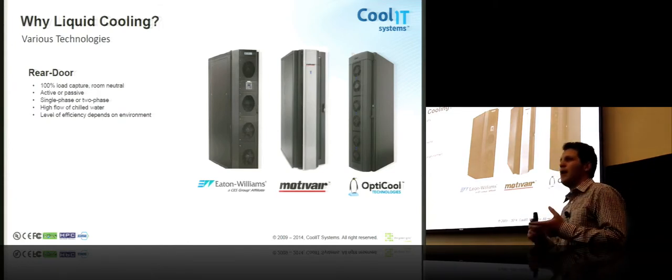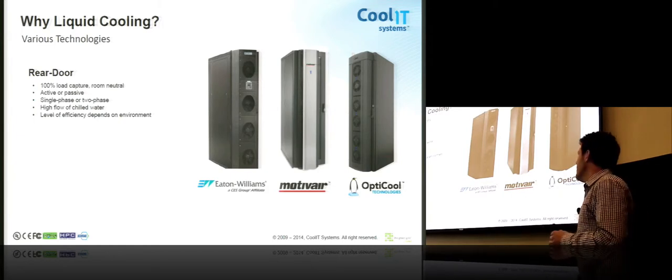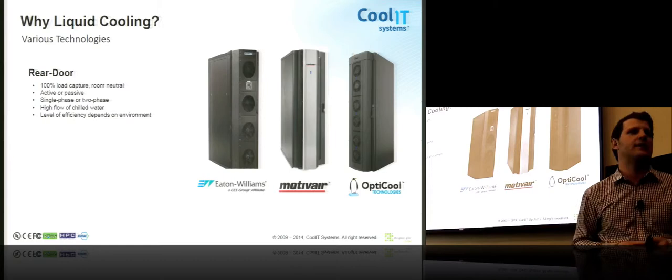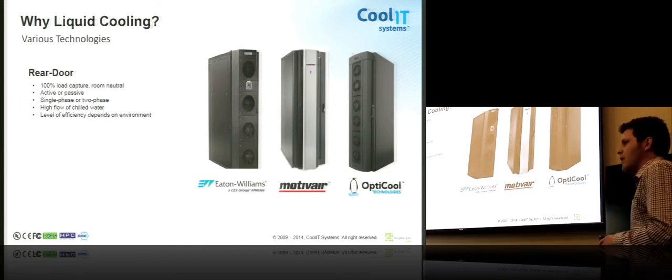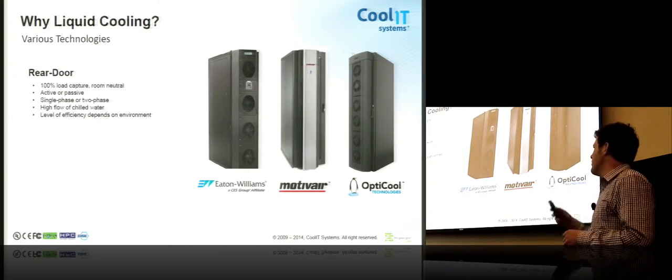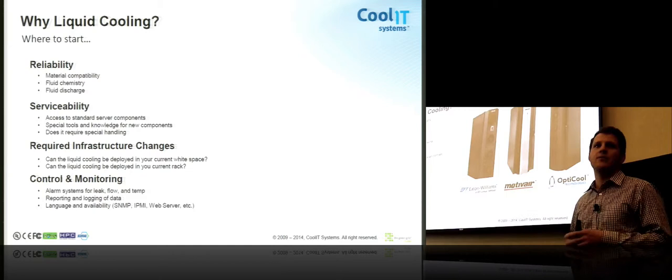These also fit onto all common racks. So if you have some hotspots, you have some high-density racks that are sitting next to standard, maybe lower-density racks, to put a rear door on that rack is not that difficult anymore. The downside with rear doors is that you do need a relatively high flow of low-temperature water. So again, mileage will vary. The efficiency depends on the environment that you're in and the region that you're in.